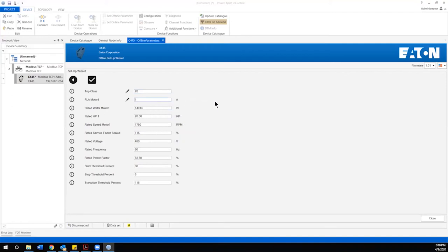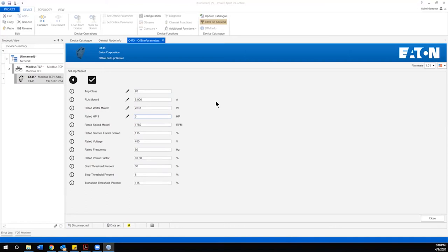Second we need to enter the full load amp for the motor. In this case I'm using a 5 amp example. I'm then going to click all the way down to the rated horsepower and you'll notice that as I establish the horsepower and enter that it is then going to update the watts. The next parameter we want to update is the rated speed of the motor. We're going to use this four pole example of 1750.